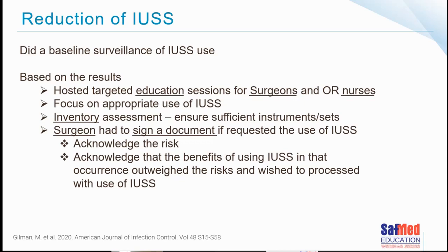They wanted to focus on the appropriate use of immediate use steam sterilization. So if you did have to use it, that it was used correctly. Of course, to do that, one of the important things is to assess all of your inventory, because you don't want to be flashing because you don't have enough instruments. That's not the real correct reason for using immediate use steam sterilization. So they ruled that out and overcame those issues.